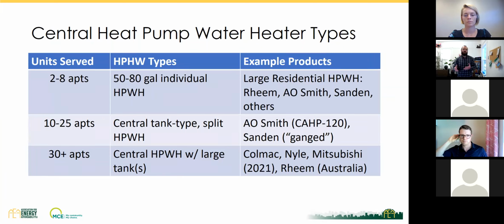On a small number of apartments, you could probably get away with a single individual tank-type heat pump hot water heater. On maybe 10 to 25 apartments, you have some options about which route you want to take. And then on big buildings, you're typically going to need a large heat pump hot water heater and a large volume of storage.